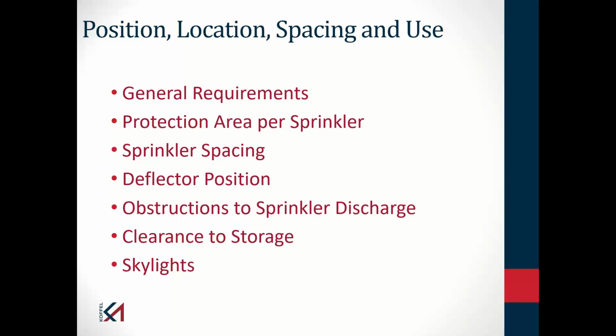So again, if I go back to that office, if that office happened to be 200 square feet and it had a single sprinkler in it, and I'm now converting it to a storage use where my spacing might need to be 130 square feet per sprinkler, I may need to add another sprinkler in that space.